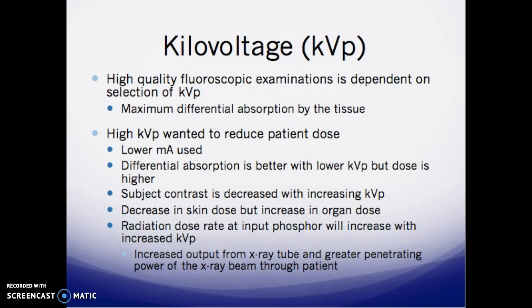There is maximum differential absorption by tissue. A high KVP is wanted to reduce patient dose — when KVP goes up, it drops the MA, and MA drives the dose. Differential absorption is better at lower KVP but dose is higher because it raises MA. Subject contrast decreases with increasing KVP. There is a decrease in skin dose but an increase in organ dose, because the energy is strong enough to penetrate the skin and deposit in the organs. Radiation dose rate at the input phosphor increases with increased KVP due to greater beam output and penetrability.